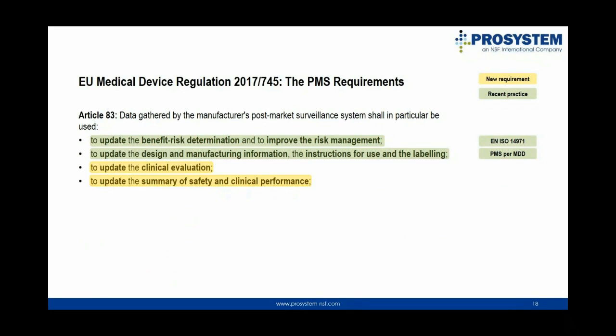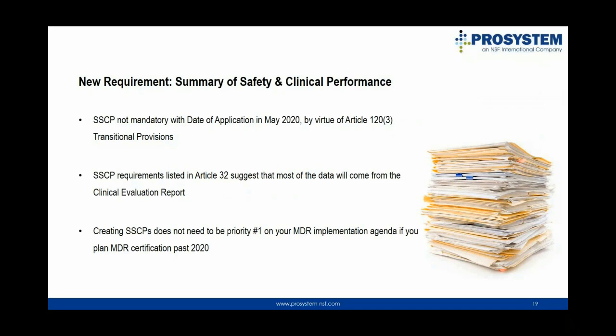So, PMS data shall also be used to update the new summary of safety and clinical performance, or the SSCP, which the MDR introduces in Article 32, and which is required for Class 3 devices and implant devices only. So the SSCP is not mandatory with the date of application in May 2020. The SSCP is required when applying for MDR certification. The SSCP requirements, such as the intended purpose, indications, target populations, therapeutic or diagnostic alternatives, which are listed in Article 32, suggest that most of the data may be extracted from the clinical evaluation report.